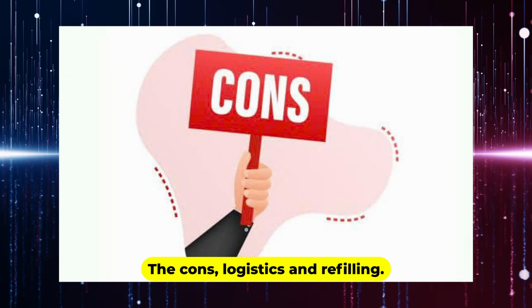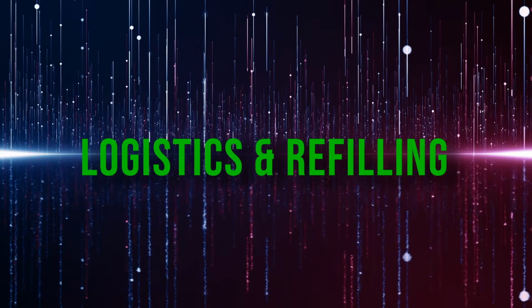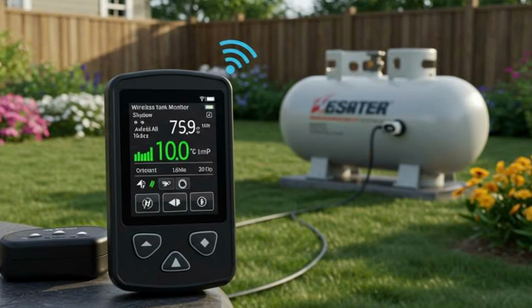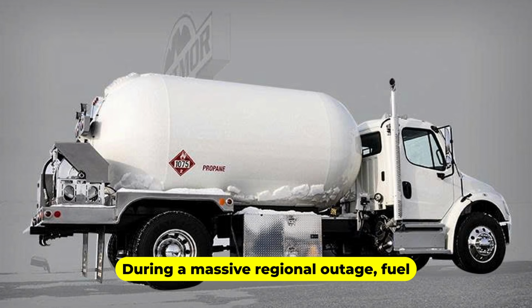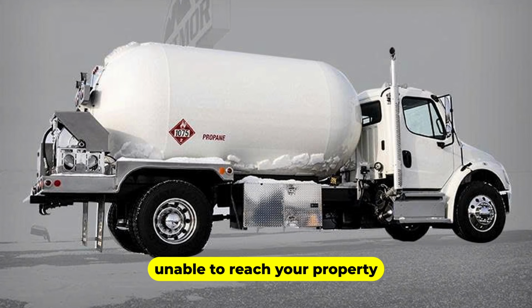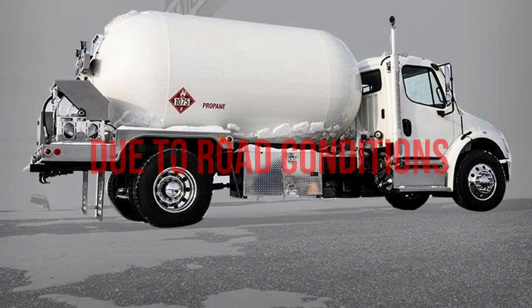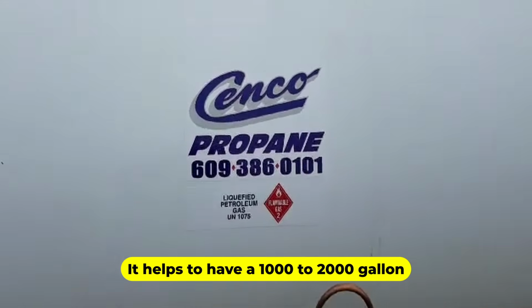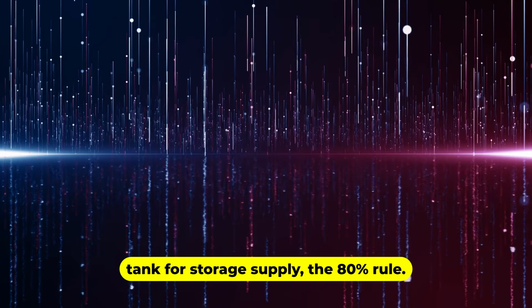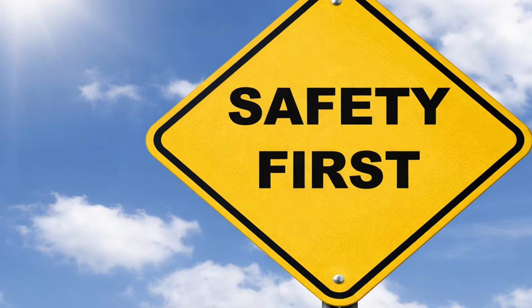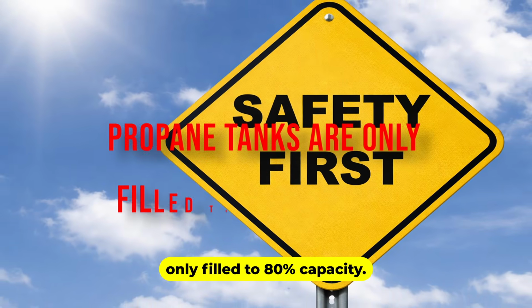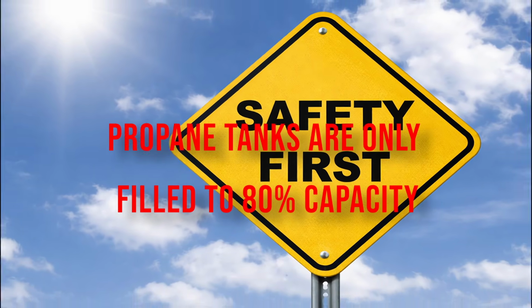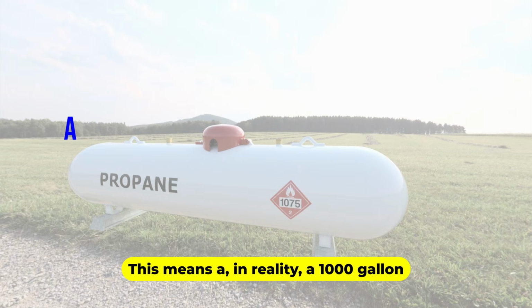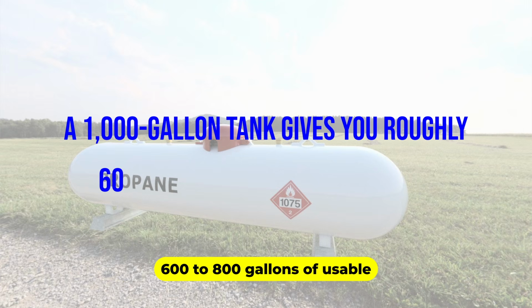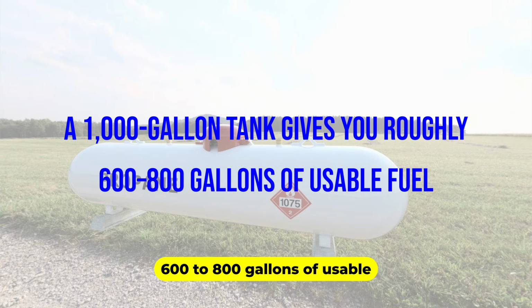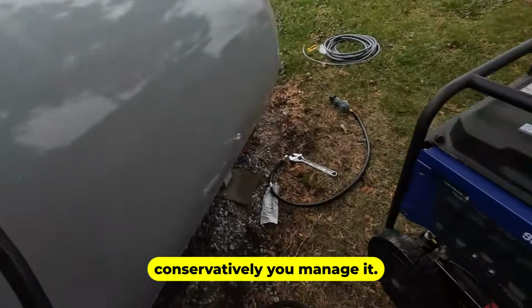The cons: Logistics and refilling. You must monitor your tank levels. During a massive regional outage, fuel delivery trucks may be unable to reach your property due to road conditions. It helps to have a 1,000 to 2,000 gallon tank for storage supply. The 80% rule. For safety, propane tanks are only filled to 80% capacity. This means in reality, a 1,000 gallon tank gives you roughly 600 to 800 gallons of usable fuel depending on how conservatively you manage it.